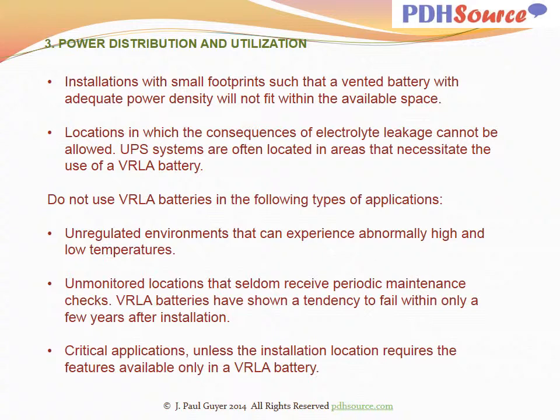Do not use VRLA batteries in the following types of applications. Unregulated environments that can experience abnormally high and low temperatures. Unmonitored locations that seldom receive periodic maintenance checks. VRLA batteries have shown a tendency to fail within only a few years after installation. Critical applications, unless the installation location requires the features available only in a VRLA battery.